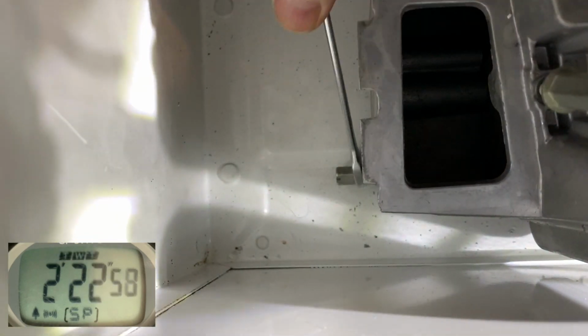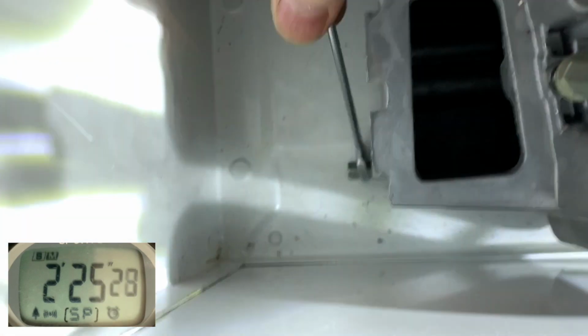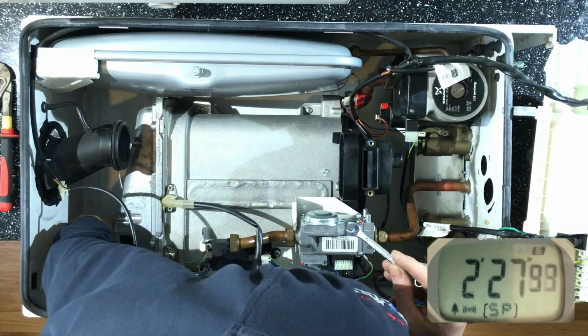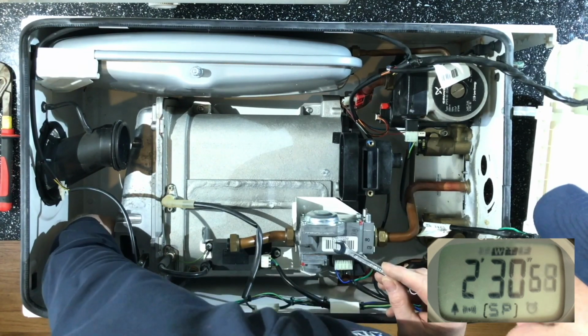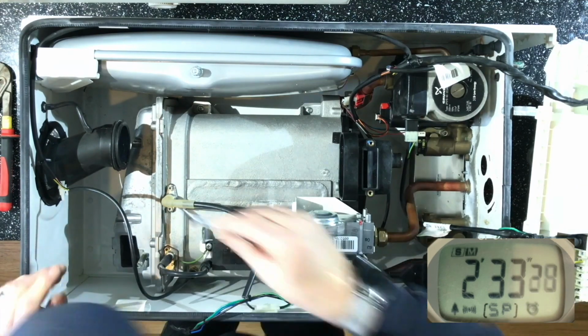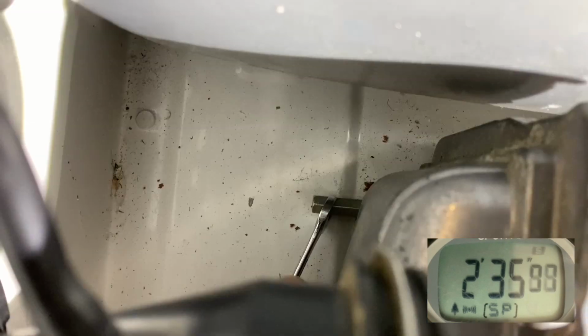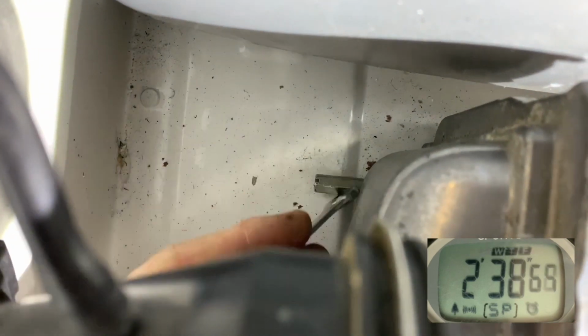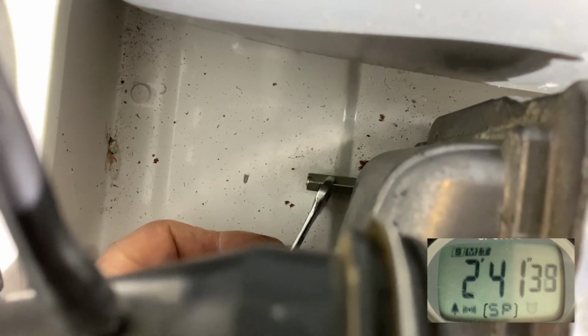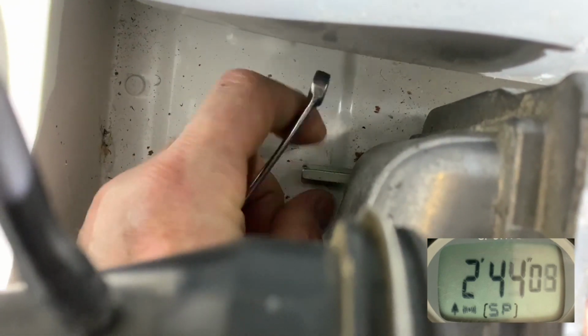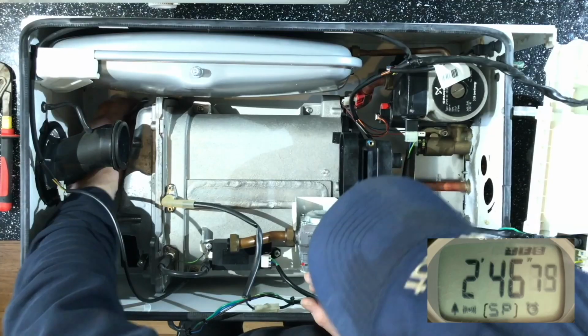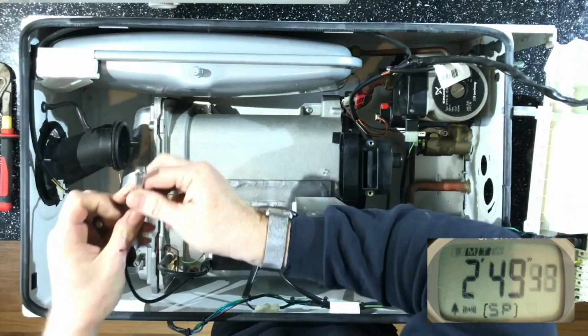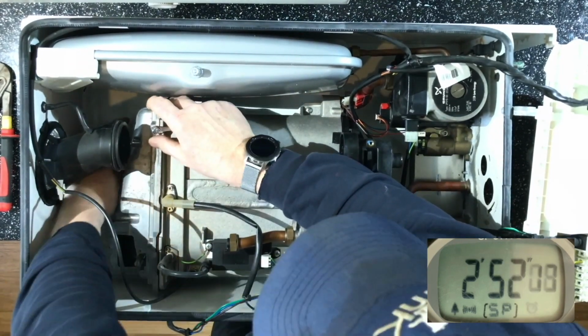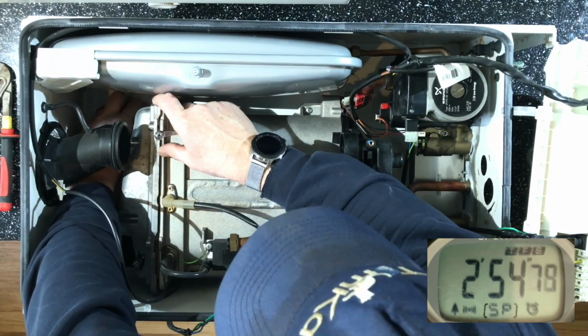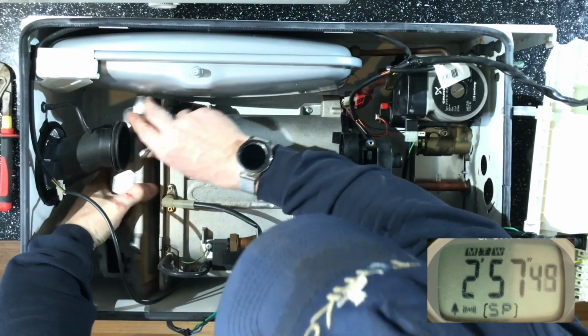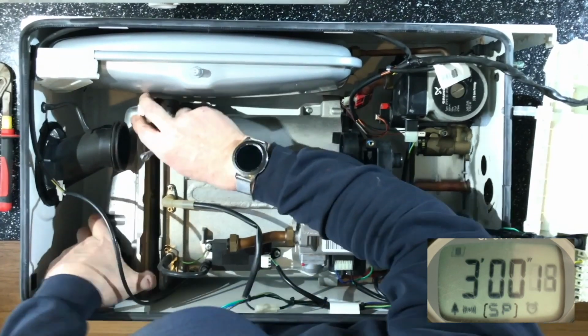Now the two at the front are a lot shorter than the ones at the back, so you can see I'm struggling to get the ones at the back off, and this is why they make them a lot higher. Now this one is easier to get off than the one I'm trying to get off now. That is a pain, so this is probably the worst one, but you don't have to take these all the way off, you just need to slacken them to be able to remove the burner, which you're going to find I'm going to struggle to do, because it's a lot easier to take the burner off when it's actually on the wall, believe it or not, than when it is laid down on its back like this.